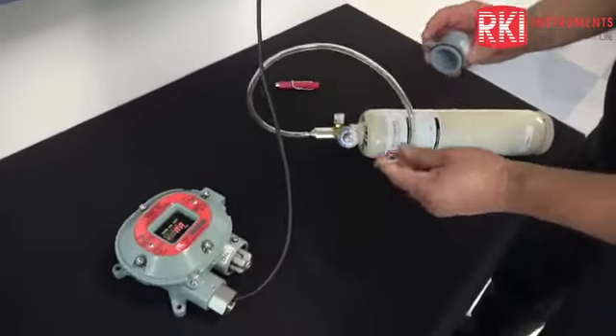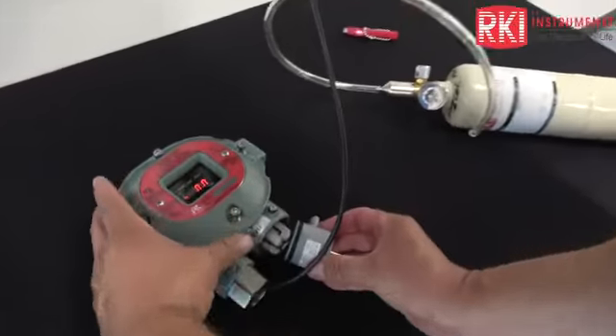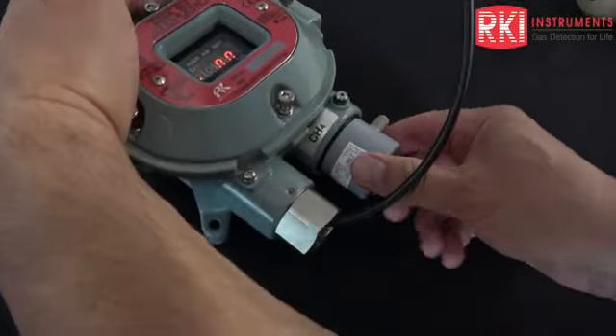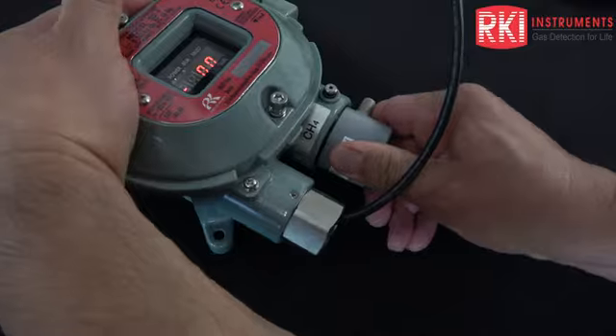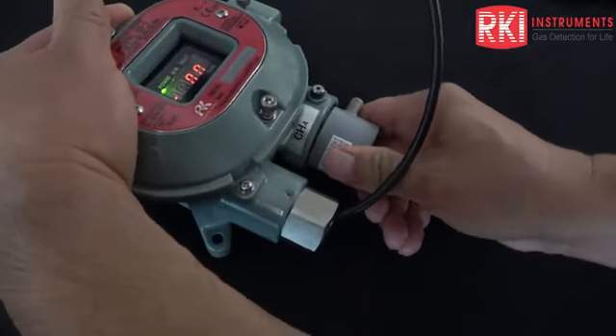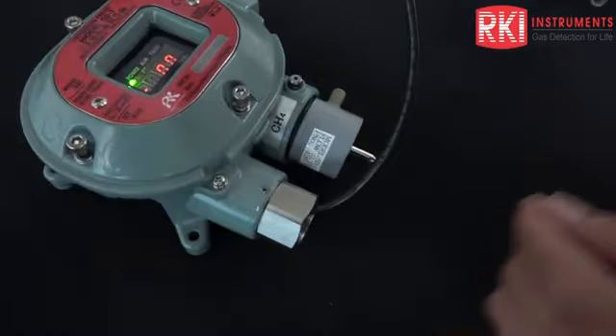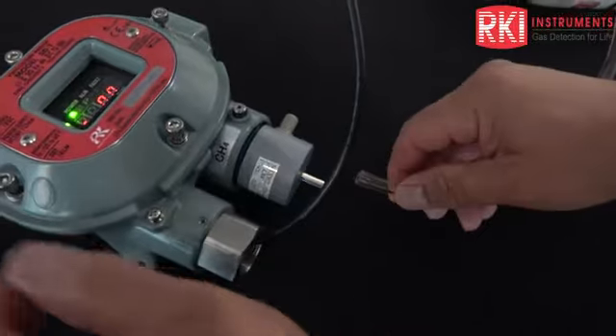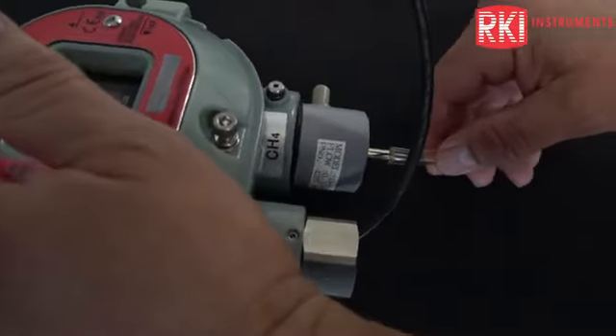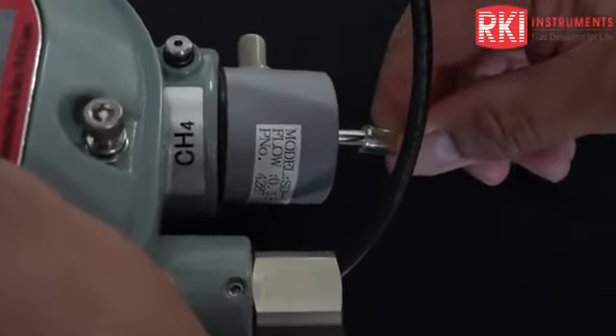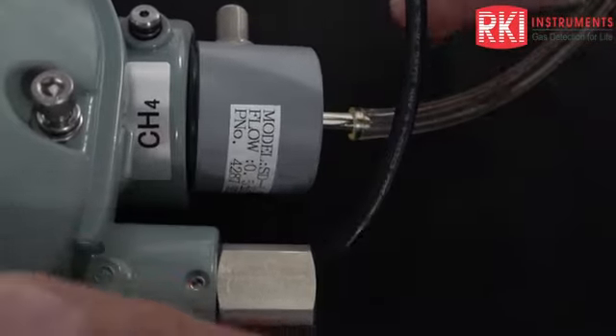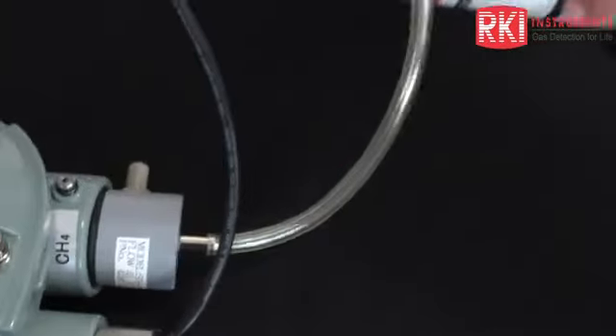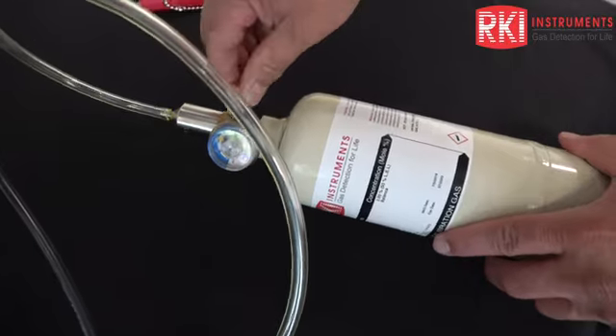So now I'm going to get my cal cup on here, and I just want to push that on, get a reasonable seat, a nice tight, there, that's good enough. And then put my other end of the tubing on the nipple, the gas end nipple. Okay, and now I'm going to open up the valve to the regulator and flow that gas at half a liter per minute.